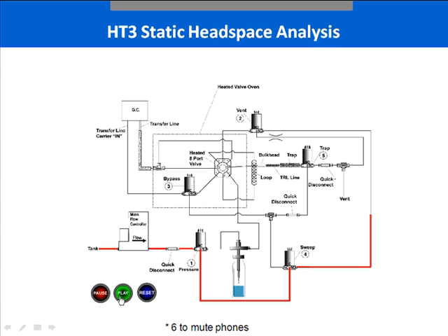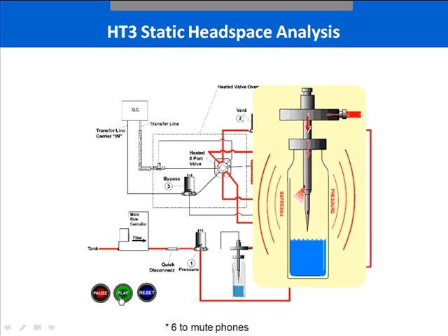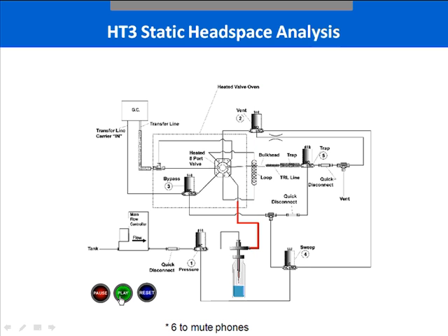The gas comes into the HT3 to pressurize the vial in the first step — that is the sample path it takes. At this point, the vial is being pressurized. It is then released into the loop at a set amount of time, filling the loop with a consistent volume. Once that filling has been performed, the loop is shut off and put into line with the GC chromatograph.